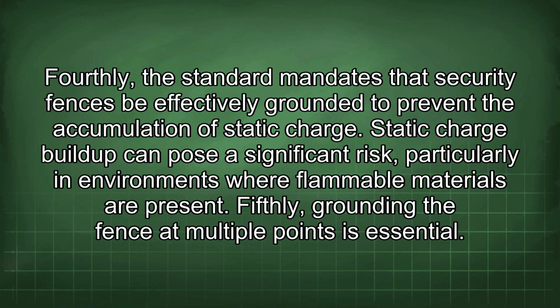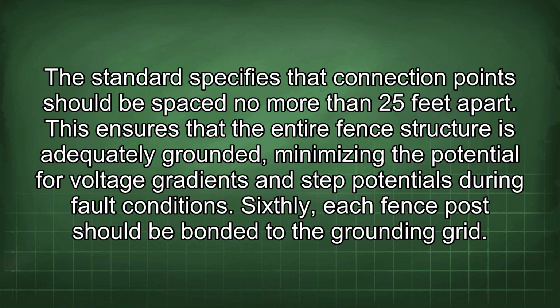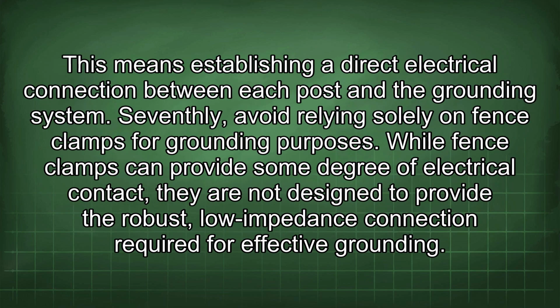Fifthly, grounding the fence at multiple points is essential. The standard specifies that connection points should be spaced no more than 25 feet apart. This ensures that the entire fence structure is adequately grounded, minimizing the potential for voltage gradients and step potentials during fault conditions. Sixthly, each fence post should be bonded to the grounding grid. This means establishing a direct electrical connection between each post and the grounding system.